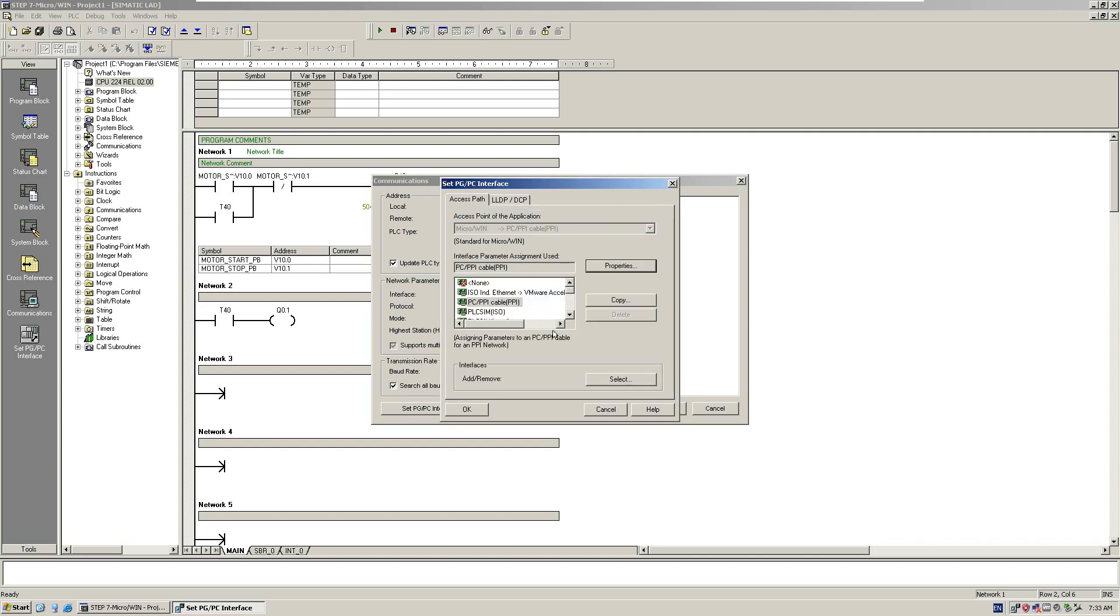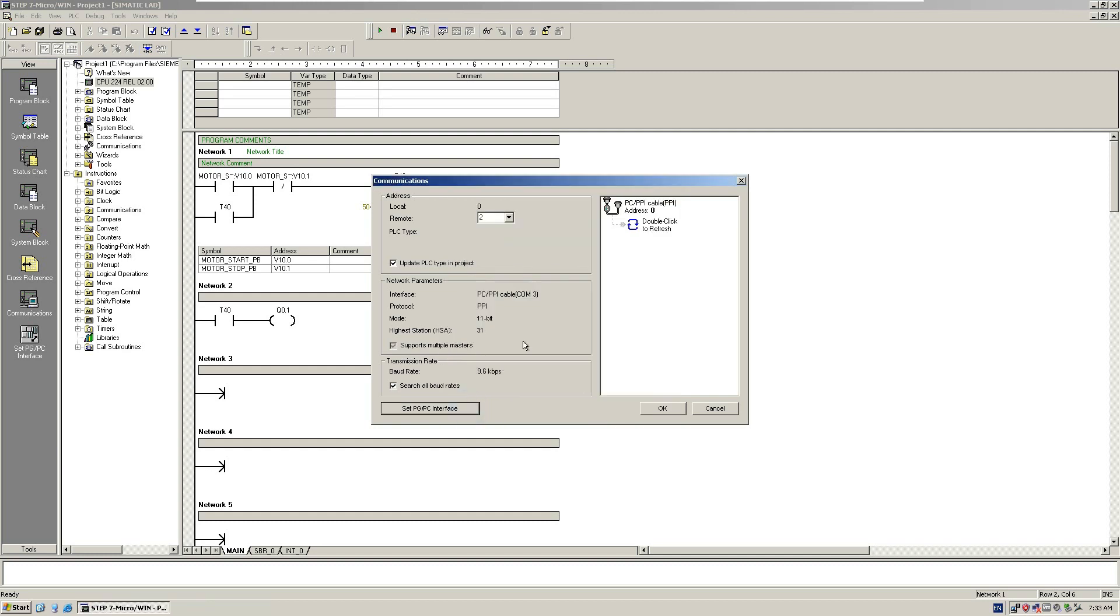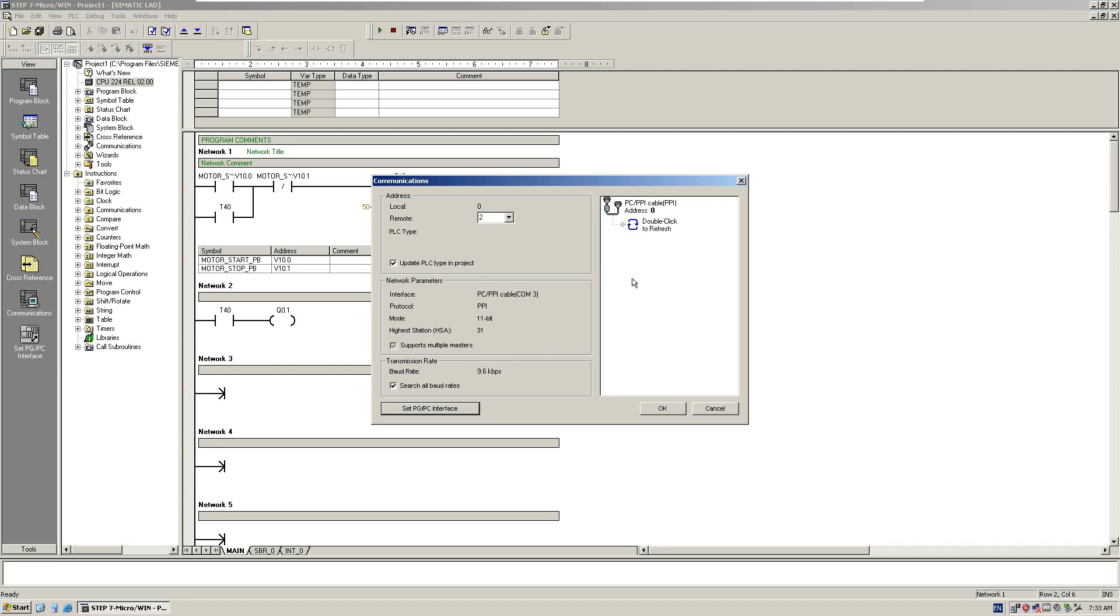Click OK. When you click OK, we can see an overview of your settings: PC-PPI cable COM3, protocol is PPI, and the initial speed is 9.6 kilobits per second. Take care of this checkbox: search all baud rates. This allows your software to scan the controller with all transmission rates. Check on this box. From here, we double-click to refresh.